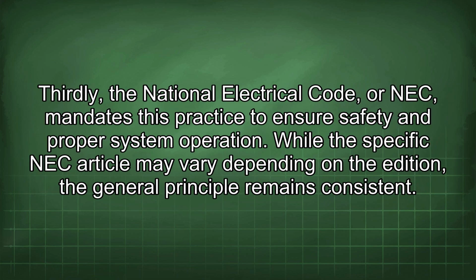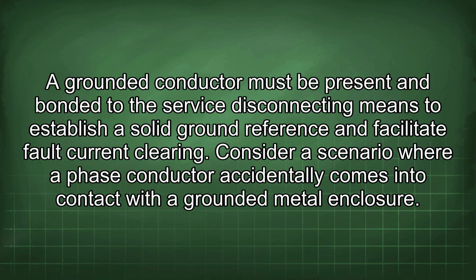Thirdly, the National Electrical Code, or NEC, mandates this practice to ensure safety in proper system operation. While the specific NEC article may vary depending on the edition, the general principle remains consistent. A grounded conductor must be present and bonded to the service disconnecting means to establish a solid ground reference and facilitate fault current clearing.